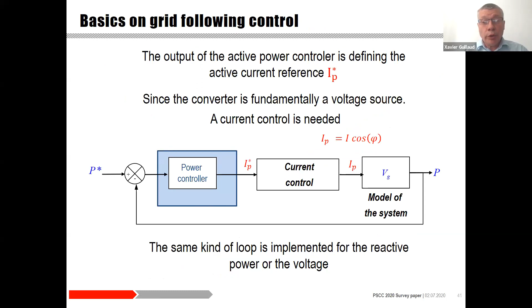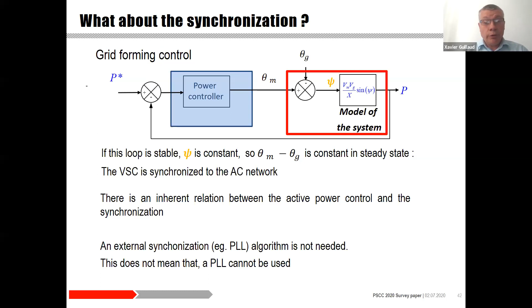Let's see now the influence of the choice of the active power control on the way to synchronize the VSC to the grid. Let's start with a grid forming control. We recall the very basic power loop. If this loop is stable, then psi is constant. Then the difference between theta m and theta g is constant. I recall that theta g is the grid angle, and theta m is the voltage angle modulated by the VSC. If this difference is constant, then in steady state, it means that the VSC is synchronized to the AC grid. An external synchronization, such as a PLL, is not compulsory.